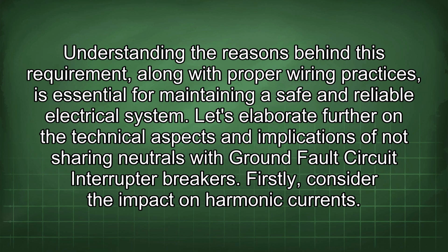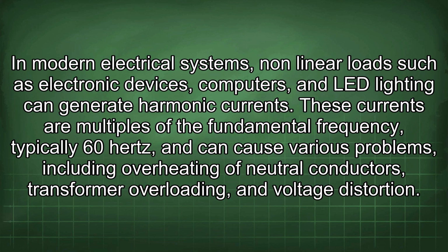Firstly, consider the impact on harmonic currents. In modern electrical systems, nonlinear loads such as electronic devices, computers, and LED lighting can generate harmonic currents. These currents are multiples of the fundamental frequency, typically 60 Hz, and can cause various problems, including overheating of neutral conductors, transformer overloading, and voltage distortion.